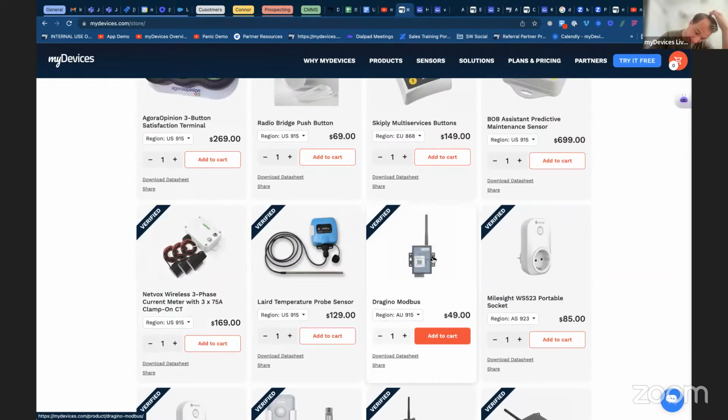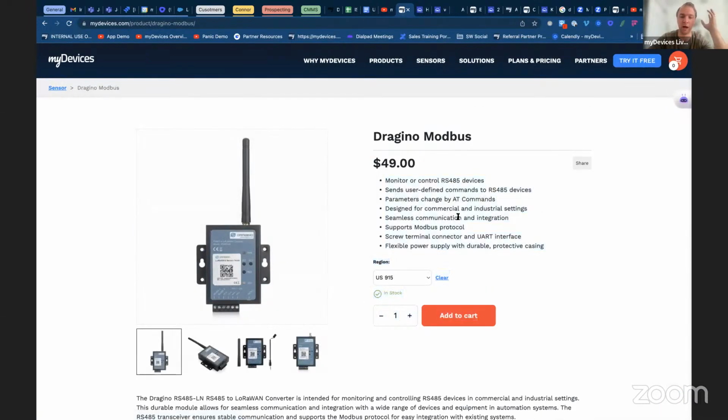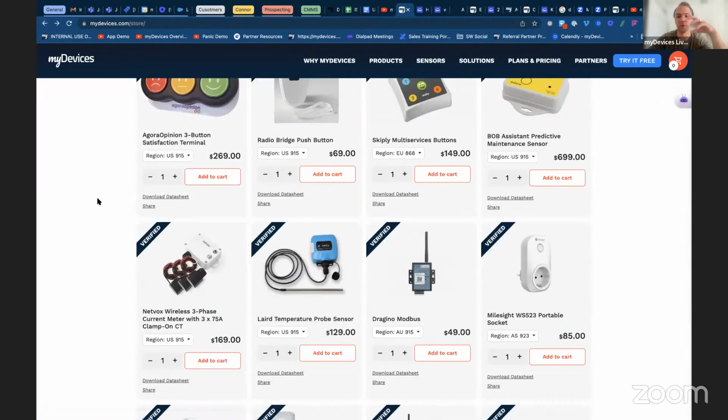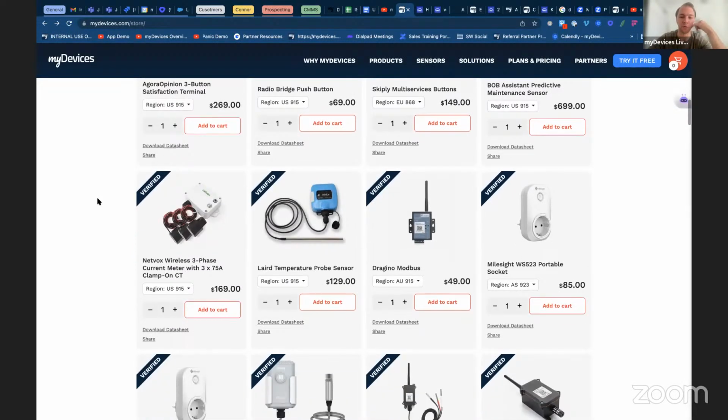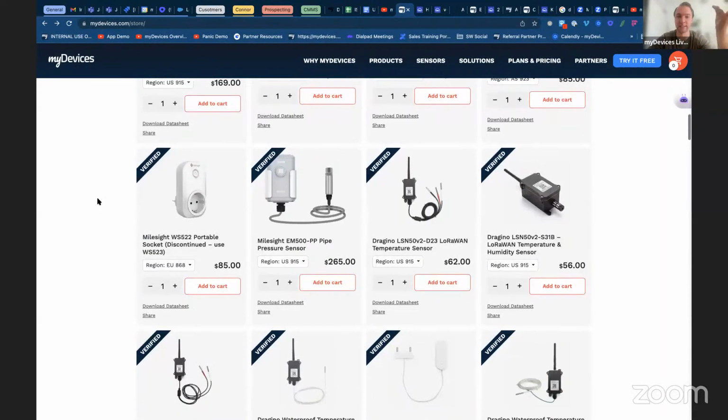Another thing with buildings is a lot of times we run into building management platforms that exist that are legacy, and maybe they have Modbus output, so we can pull out Modbus data through an RS-485 device. Maybe they have a BACnet system. We've got gateways that can pull out BACnet data. So there's retrofits that happen as well. Those legacy systems, they want remote access and control.